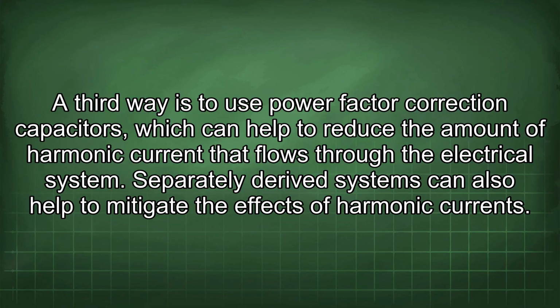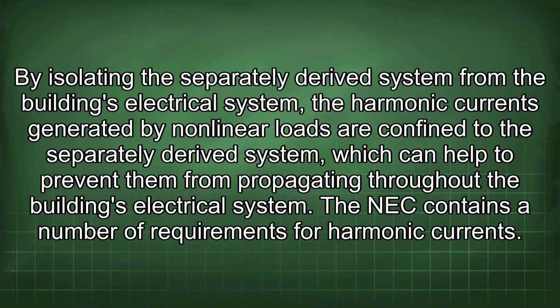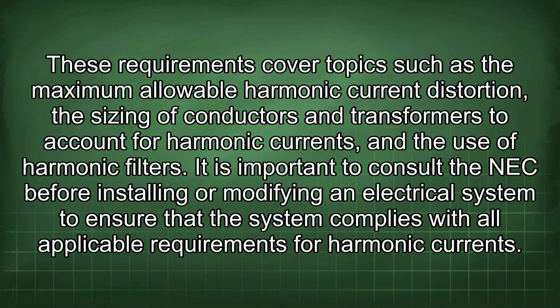Separately derived systems can also help to mitigate the effects of harmonic currents. By isolating the separately derived system from the building's electrical system, the harmonic currents generated by nonlinear loads are confined to the separately derived system, which can help to prevent them from propagating throughout the building's electrical system. The NEC contains a number of requirements for harmonic currents. These requirements cover topics such as the maximum allowable harmonic current distortion, the sizing of conductors and transformers to account for harmonic currents, and the use of harmonic filters. It is important to consult the NEC before installing or modifying an electrical system to ensure that the system complies with all applicable requirements for harmonic currents.